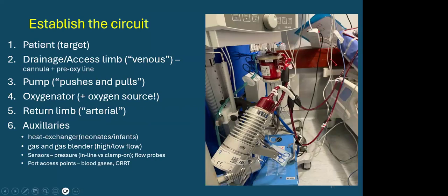And the pump, let me just see if I can grab this pointer. So that would be the venous limb coming towards the pump. Almost all current models now are centrifugal pumps. The blood enters the top, spins there and exits out the bottom, and makes the short pathway towards the oxygenator. The important thing about the oxygenator is that if it's not connected to an oxygen source, it really doesn't give much more oxygen than room air. So the little green tubing is very important to be connected to a viable oxygen source and to the correct port. A very easy thing to forget in the chaos that ensues when you're putting a patient on ECMO. And then from the oxygenator is the return limb, or the so-called arterial limb, which returns to the patient.